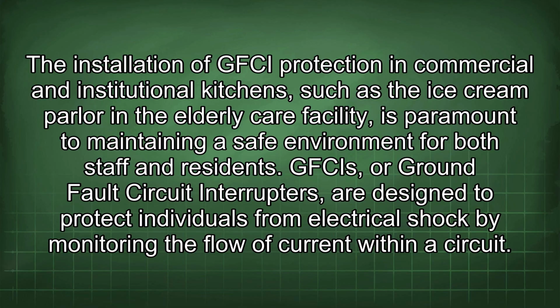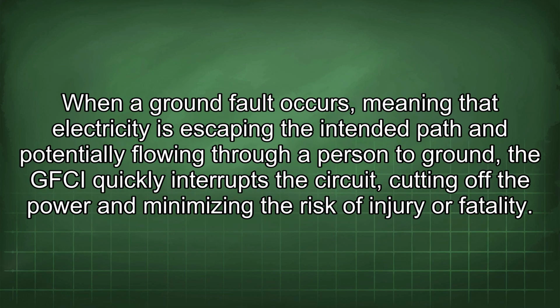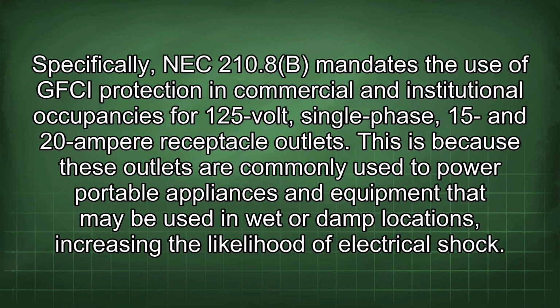GFCIs, or ground fault circuit interrupters, are designed to protect individuals from electrical shock by monitoring the flow of current within a circuit. When a ground fault occurs, meaning that electricity is escaping the intended path and potentially flowing through a person to ground, the GFCI quickly interrupts the circuit, cutting off the power and minimizing the risk of injury or fatality. Specifically, NEC 210.8b mandates the use of GFCI protection in commercial and institutional occupancies for 125-volt single-phase, 15 and 20 ampere receptacle outlets.